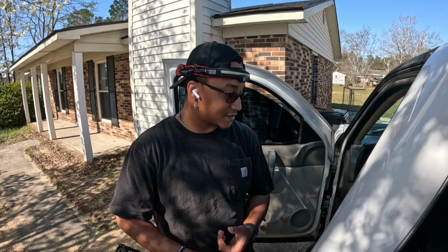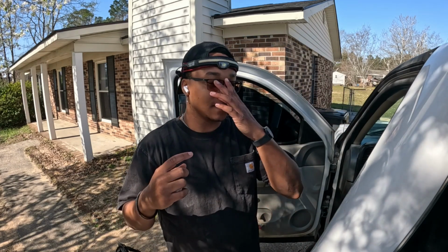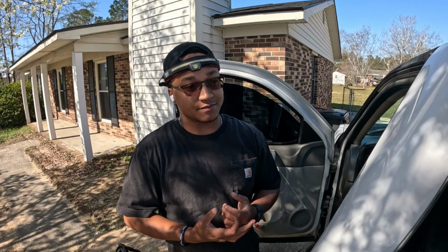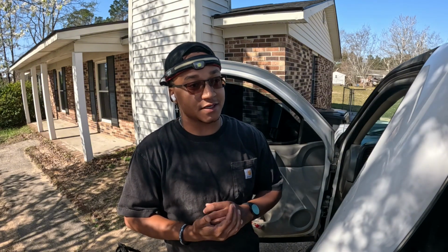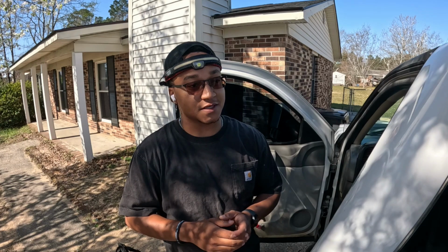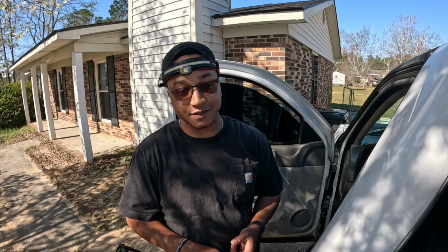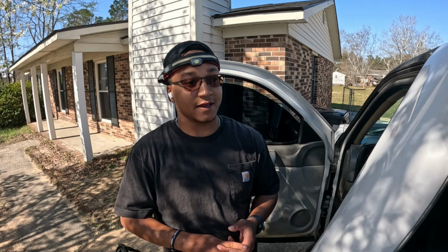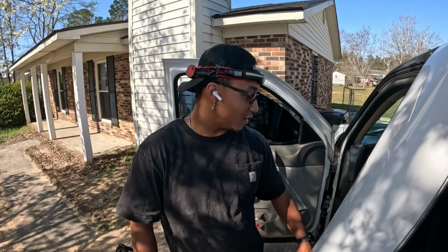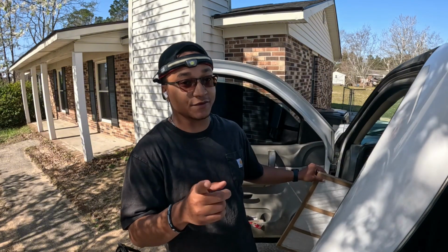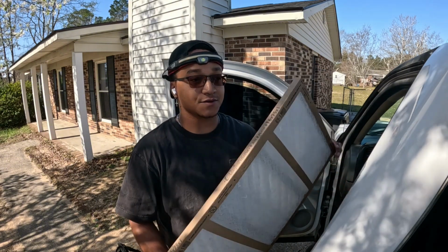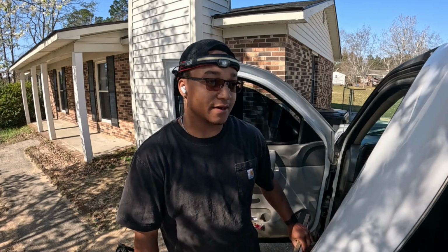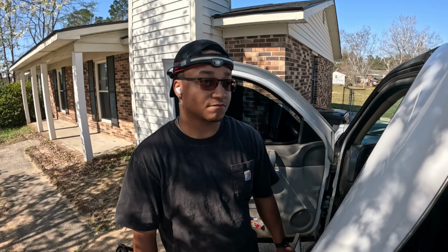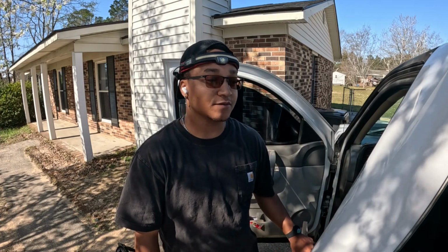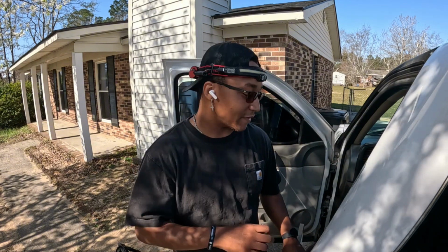So for the remainder of being inside this house working on this unit, I'm gonna work with this on and show you guys the different light setups equipped in here. This thing is bright, it's ridiculous. So let's go inside and check, I'm pretty sure it's an ECM. It's got an ECM for the blower, I don't think it's a PSC. Double check the flame sensor and just make sure airflow is good. Also, I know you guys saw the terrible filter that was in there already, got a new one so we're gonna replace that as well, and that's pretty much gonna do it for this little preventative maintenance.